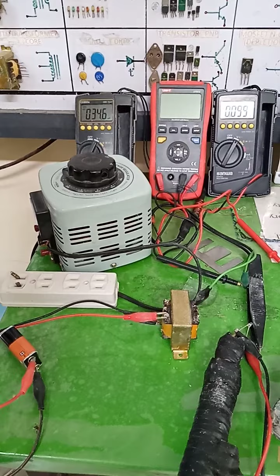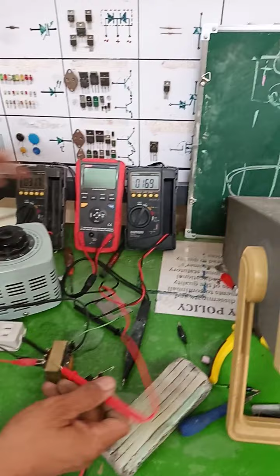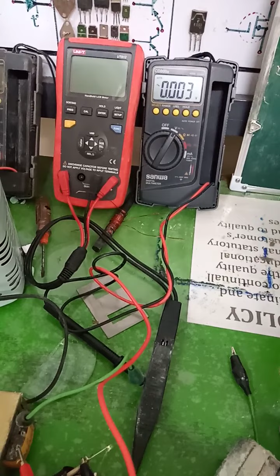Primary supplied with DC, fixed polarity. The voltage will not decrease. It is stationary 9 volts. The 9 volts being supplied to the primary is stagnant. It won't reduce, it won't increase. Stationary, permanent 9 volts. Now, this should be AC if there is really voltage at the output. So, 0. 0 volt, 0.00. Almost 0. That is practically 0 volt. So, there is no induced voltage at the secondary, although there is a primary voltage.